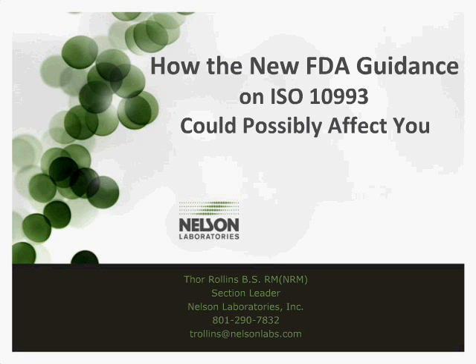Usually with webinars, I get to talk about certain tests or certain standards and how they might affect devices going forward. But this is the first time that we've really got to talk about some guidance given by the FDA that could affect medical devices. In fact, this draft document is meant to replace the G95 document that was released in 1995. So we haven't seen any kind of guidance at this magnitude for over 18 years. That's why this is quite exciting.